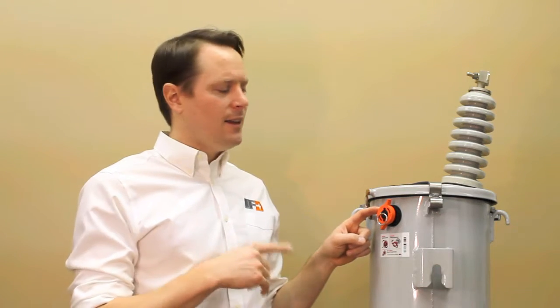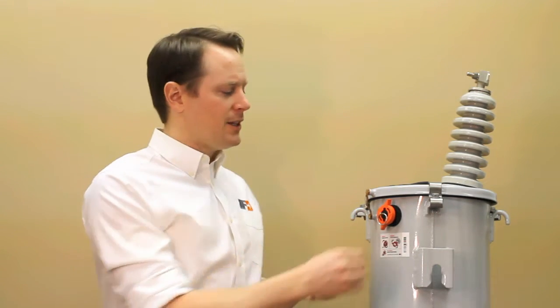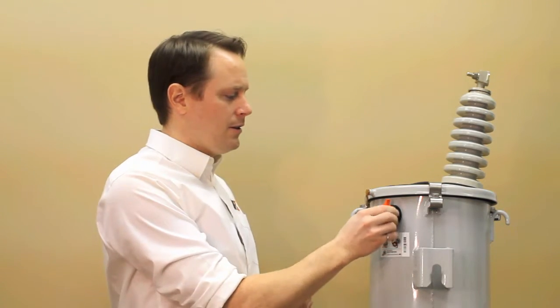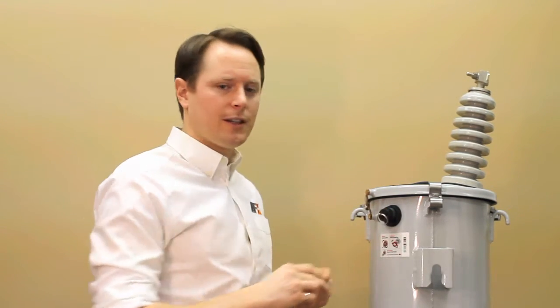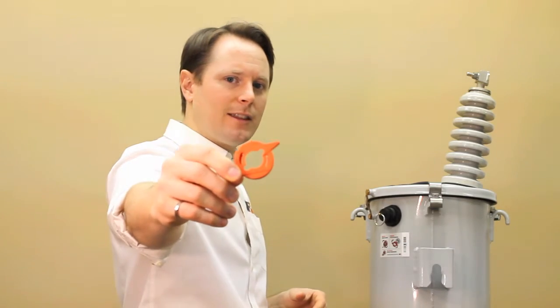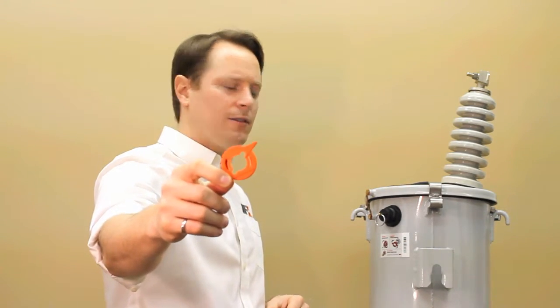It's going to protect the device whenever the transformer is moving around. So if it's in the yard or if it's moving on the back of your truck, even if it's lifting up to the position on the pole, the IFD shipping lock here is going to protect the sensor and make sure that it can deal with all of those vibrations. I'm just going to pull it off here so you can have a quicker look. It's that guy, right there. Anytime you take one off, throw it in your truck. Keep a couple hanging around. That way when you have to change out a 25 for a 50, you can just throw it right back on.